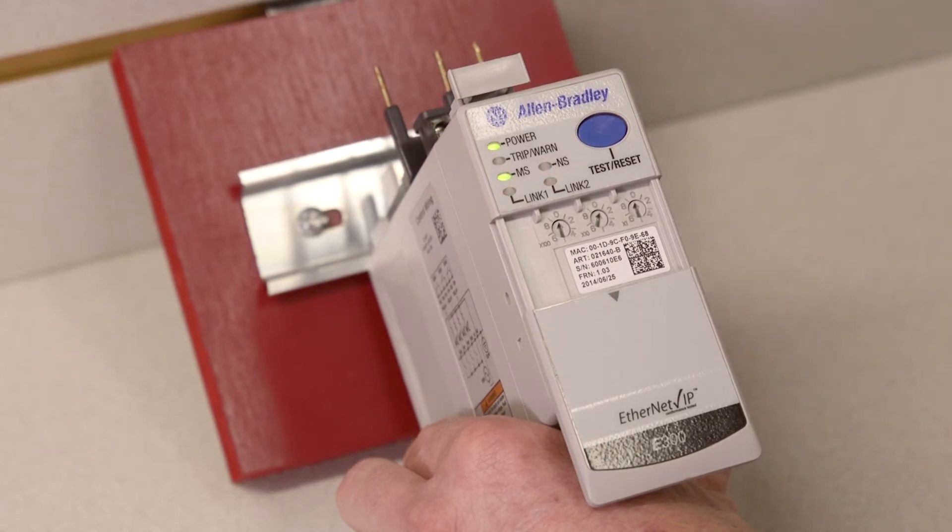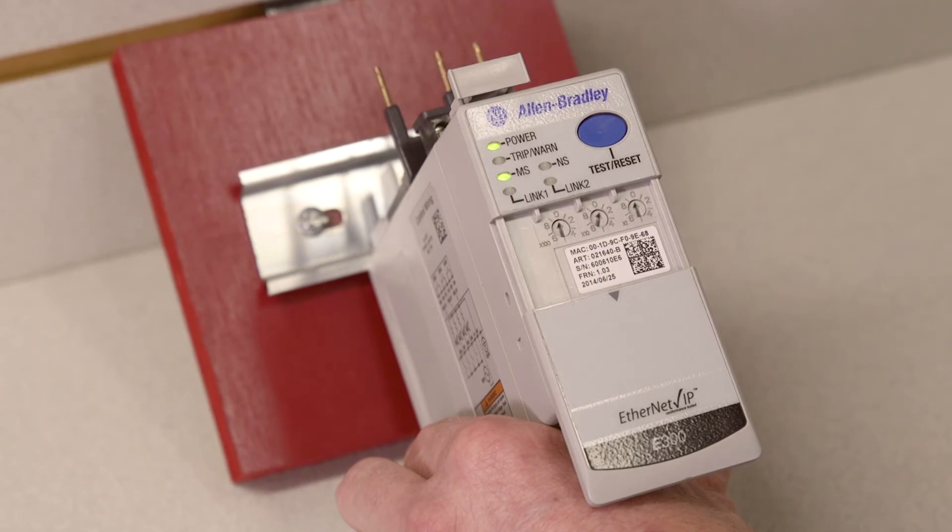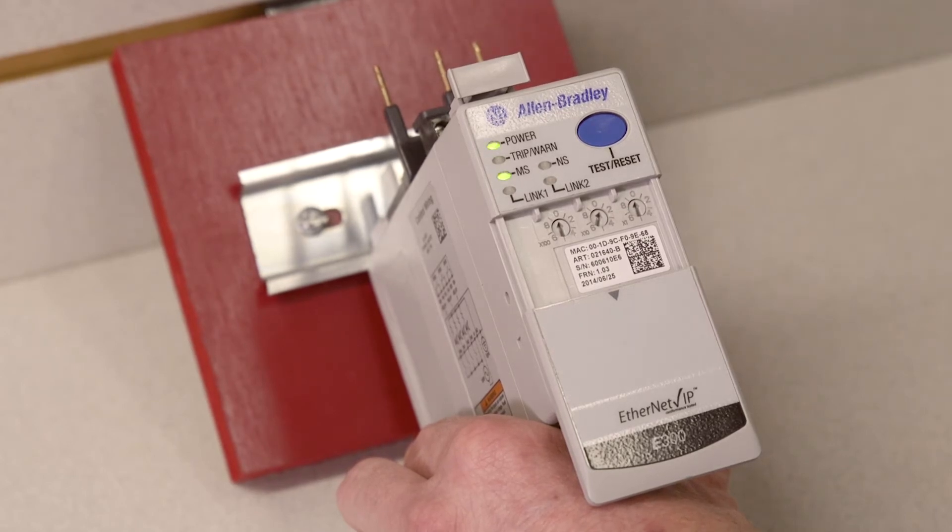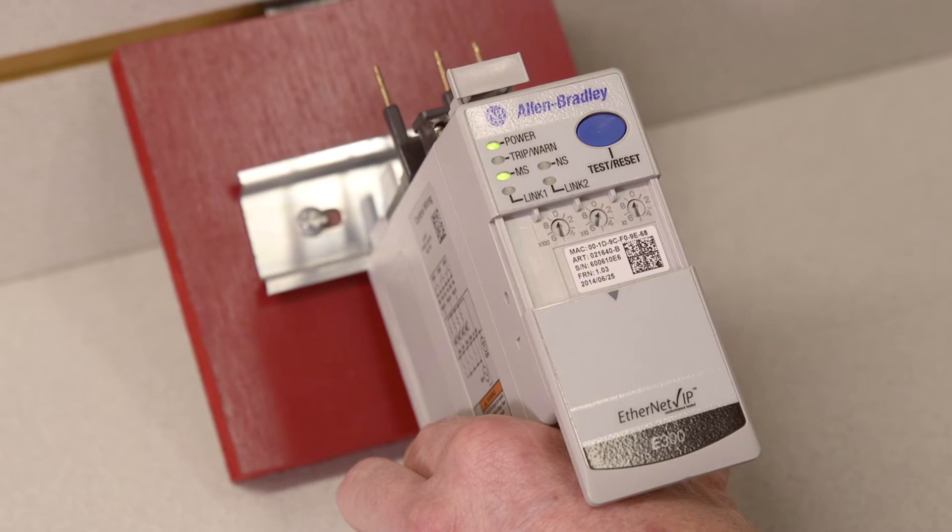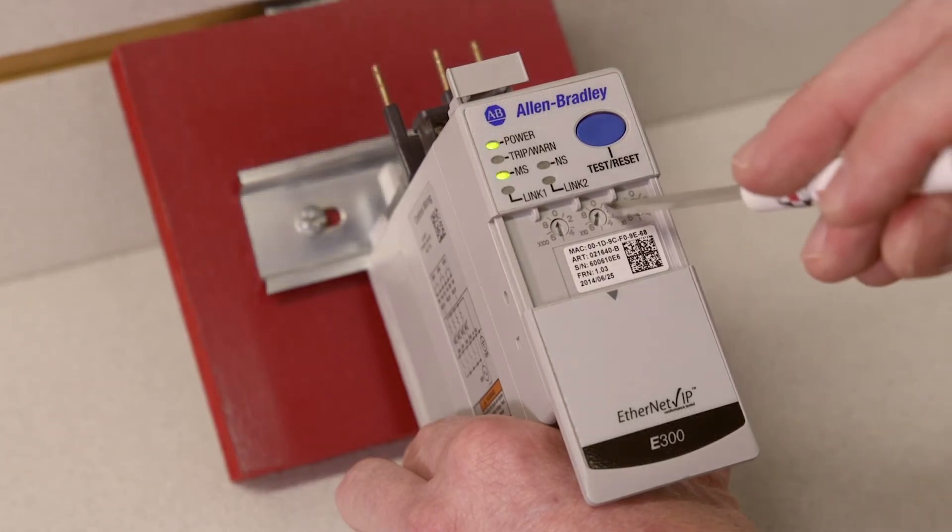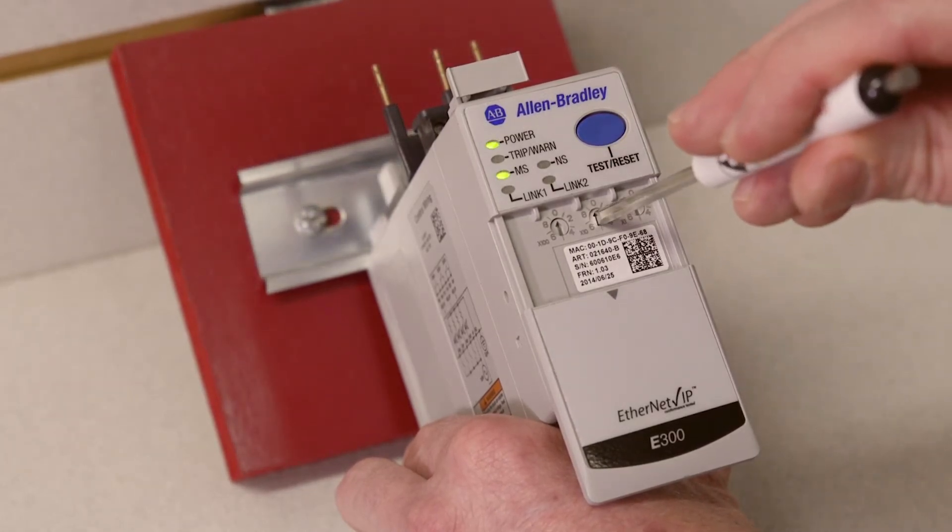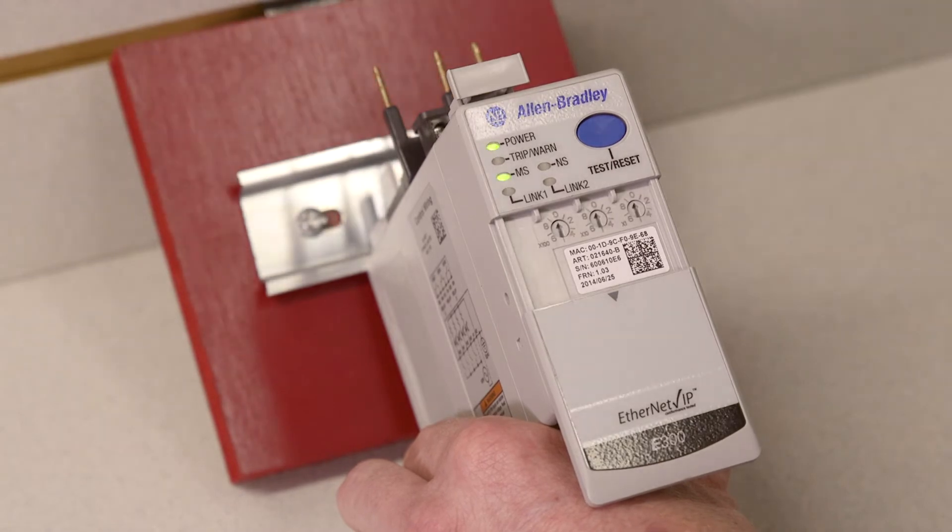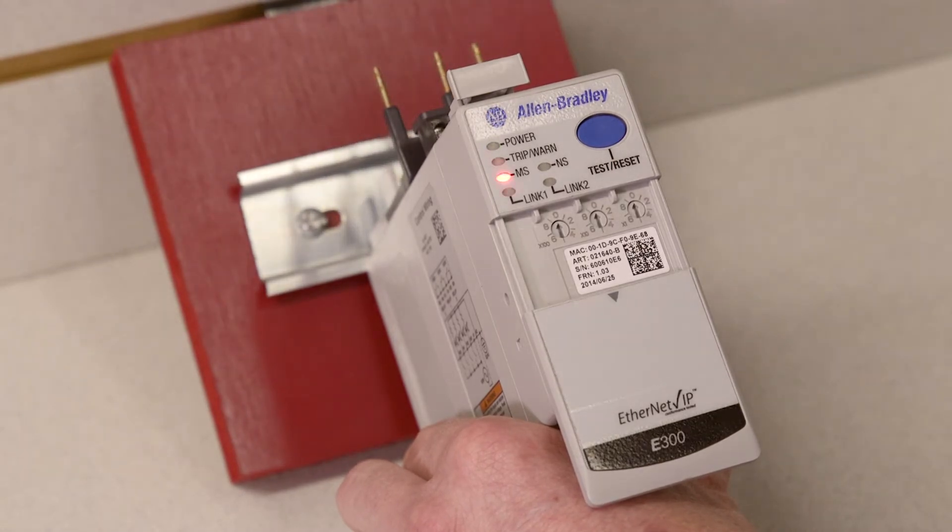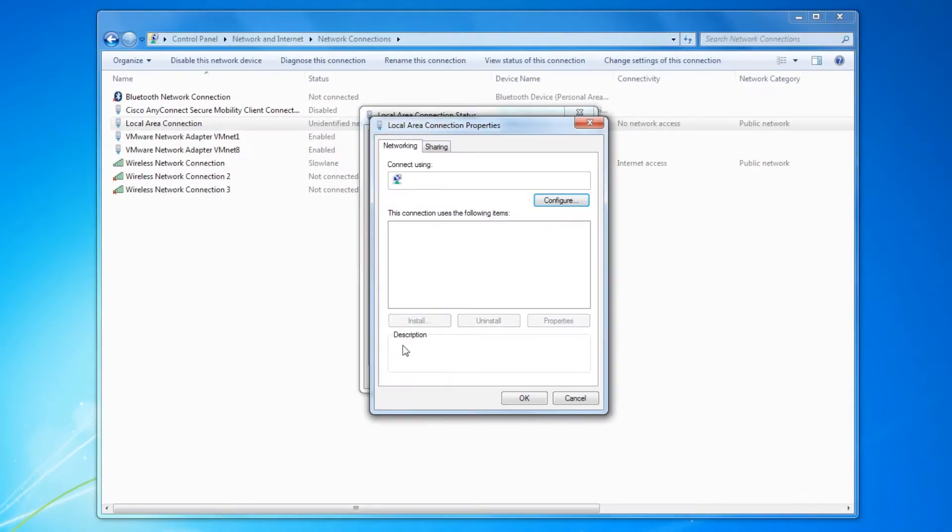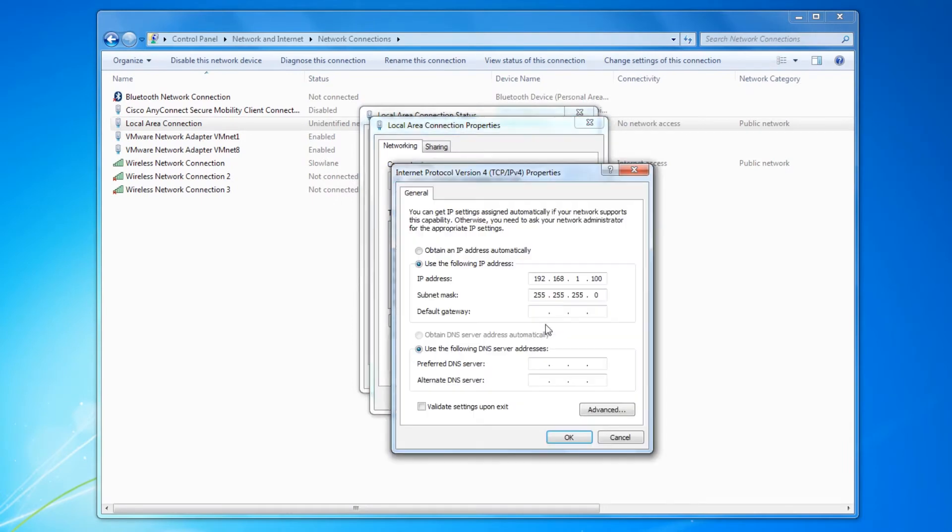Next, we will be enabling the E300 web server. Enter the administrative mode by turning the rotary dials of the E300 to 0-0-0 and cycle power. Make sure that the IP address of your computer is on the same subnet as the IP address assigned to the E300.